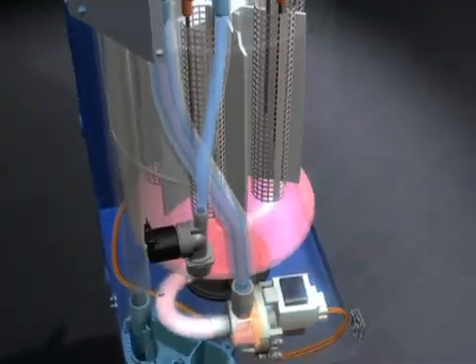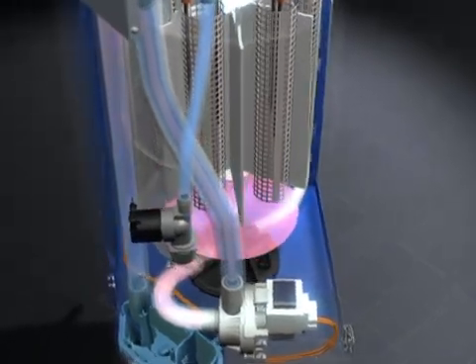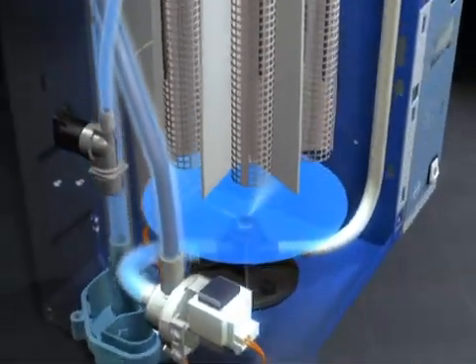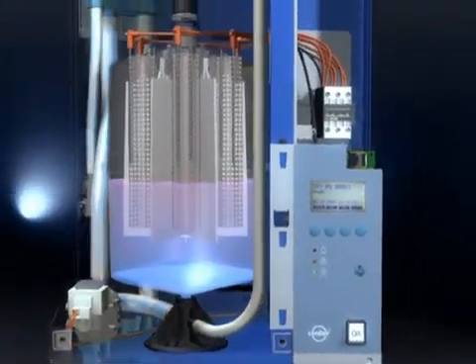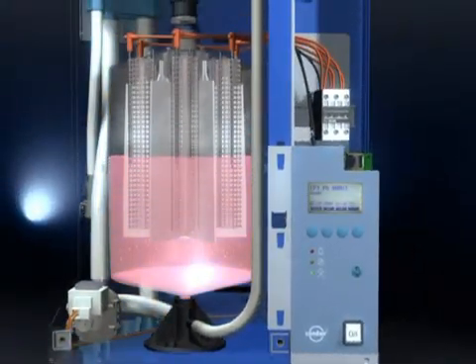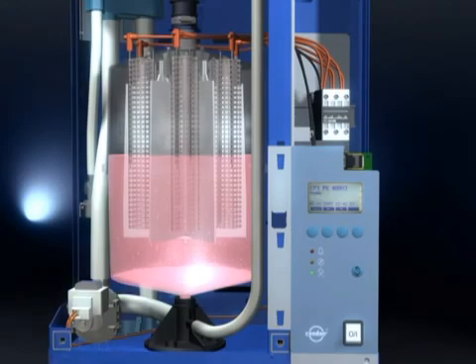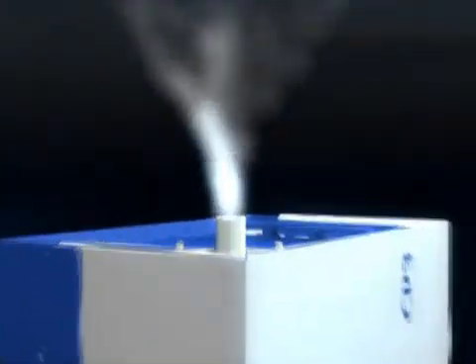During the process, the water cools down to the point where it can be evacuated without any problems through the building's piping network. Using fresh water only, the cylinder is refilled until steam output regains its appropriate level. This permanent process assures steam output throughout the entire operation.